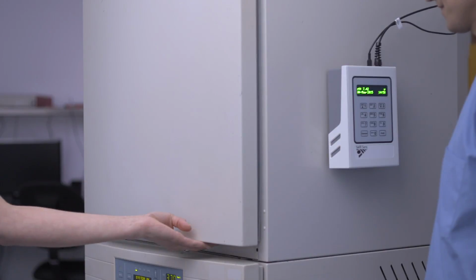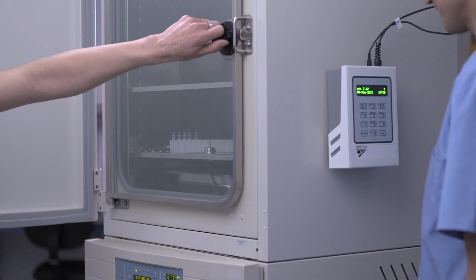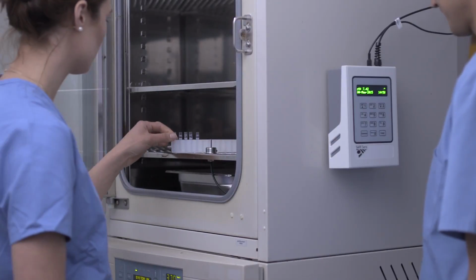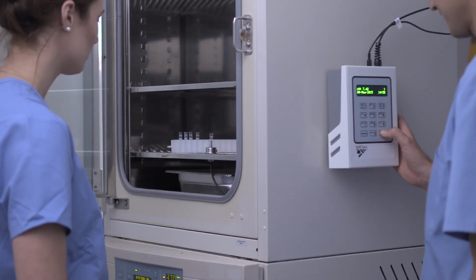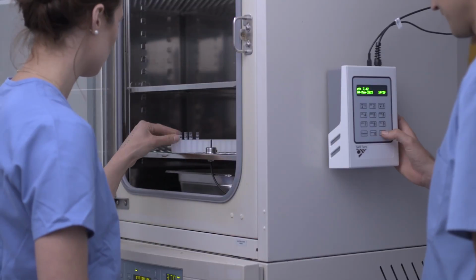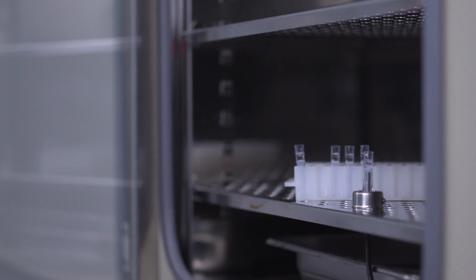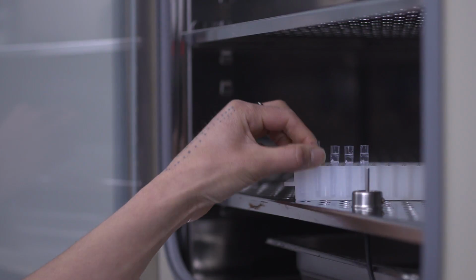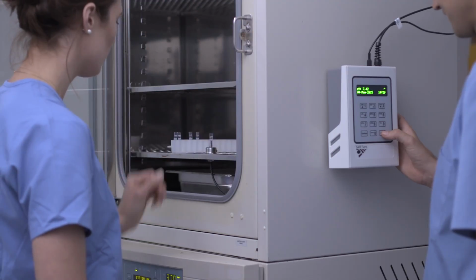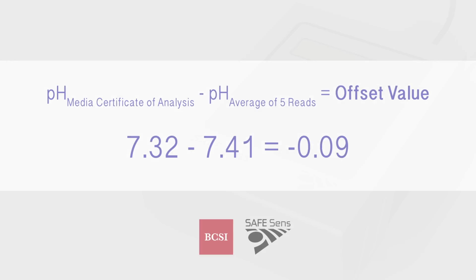Now, with the help of a second person, read all 5 of the sensors within a minute. It works best to have one person open the incubator door and put the sensor on the probe, while the other person presses Enter on the SafeSense to take pH readings and records the measured values. In the BCSI clinic, the incubator is set at 5% CO2. At 5% CO2, the certificate of analysis states the pH of the media is 7.32. The average of our measured values is 7.41. That means our offset value is 7.32 minus 7.41, or minus 0.09.